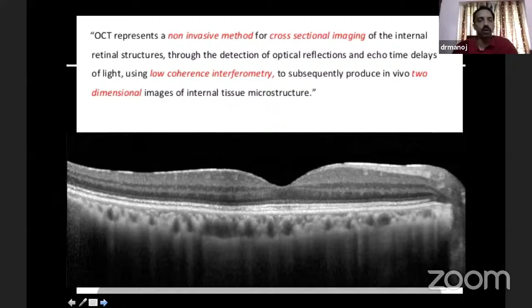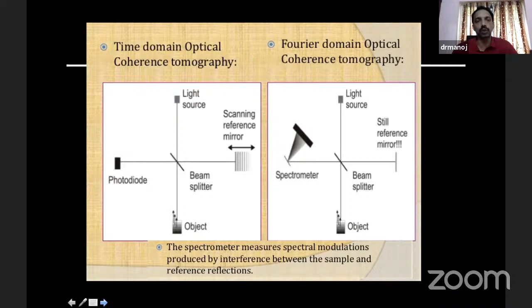I'll be introducing you to this topic, optical coherence tomography. So OCT, or optical coherence tomography, represents a non-invasive method for cross-sectional imaging of the retinal structure. It is based on the principle of low coherence interferometry. Basically, the light from these machines is split into two beams. One beam goes to the eye and the other beam goes to a scanning or reference mirror. The reflected light from the reference mirror and from the eye is integrated, and the interference between these two waves is interpreted, and that's how we understand the reflectivity of the tissue that we are studying. So this is basically the principle of interference.